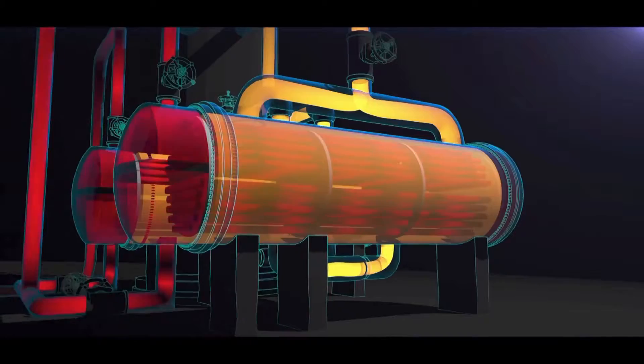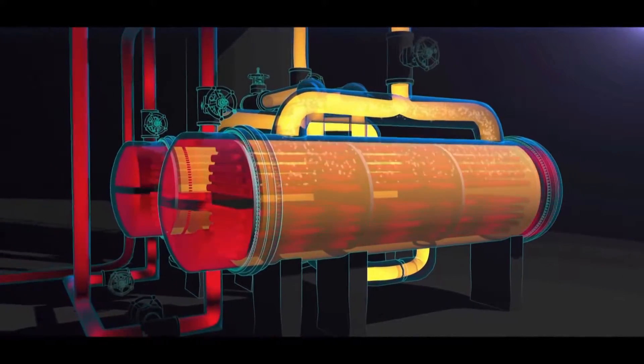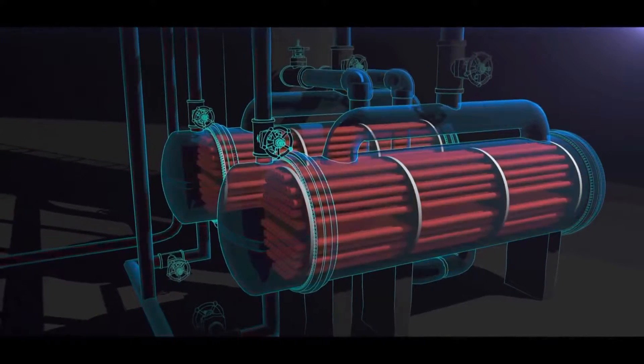The water that flows through the tubes contains a small amount of oily tar, which condenses into the water earlier in the process. Over time, the oily tar builds up on the walls of the re-boiler tubes — a buildup called fouling. Fouling reduces the efficiency of the re-boilers, so periodically they must be shut down to clean the tubes. The original propylene fractionator design had both re-boilers running simultaneously, but in that configuration, the fractionator had to be shut down when a re-boiler needed cleaning.